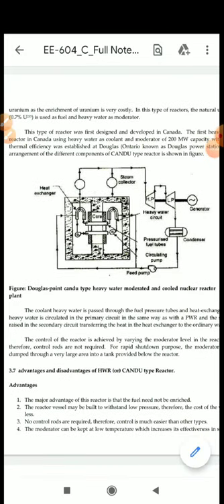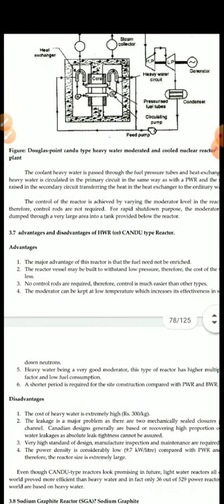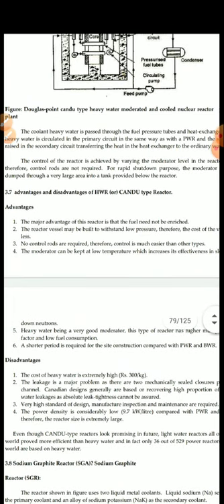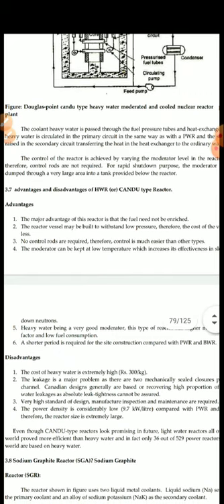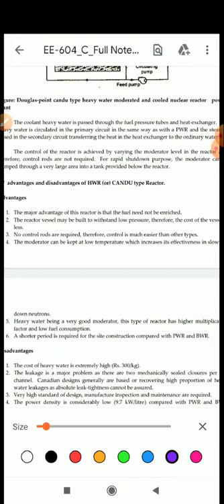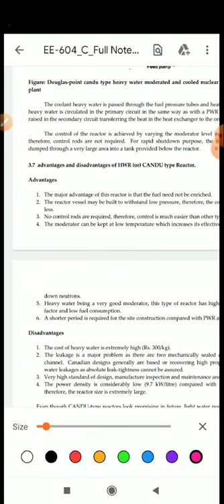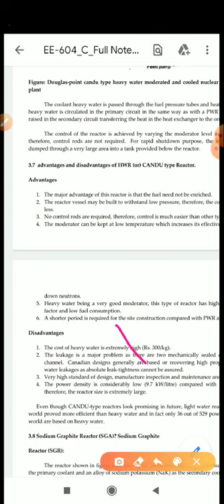So this CANDU reactor is a heavy water reactor. Let's see some advantages and disadvantages of this reactor. The advantages are: the major advantage is that the fuel need not be enriched. The reactor vessel may be built to withstand low pressure, therefore the cost of vessel is less. No control rods are required, therefore control is much easier than other types of reactors. As compared to boiling water reactor, the moderator can be kept at low temperature which increases its effectiveness in slowing down the neutron speed. The heavy water being a very good moderator, this type of reactor has high multiplication factor and low fuel consumption.